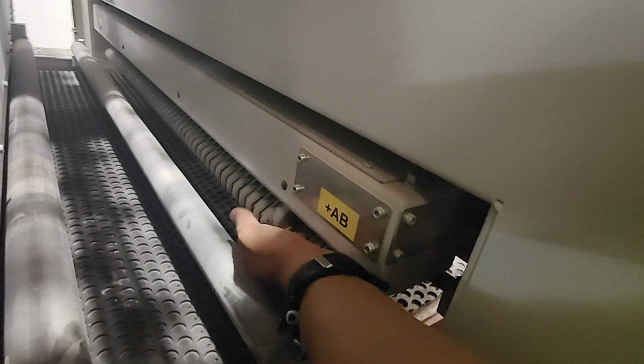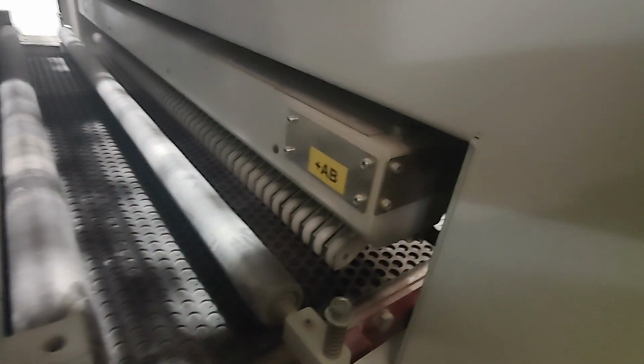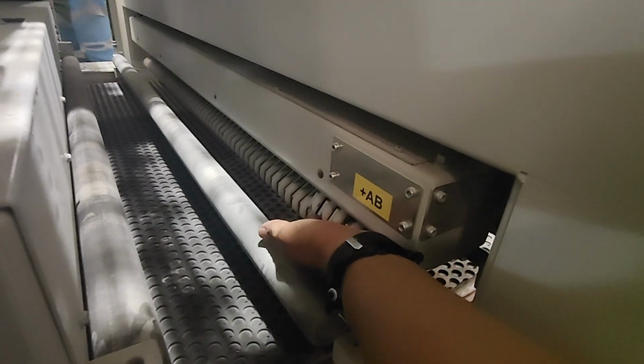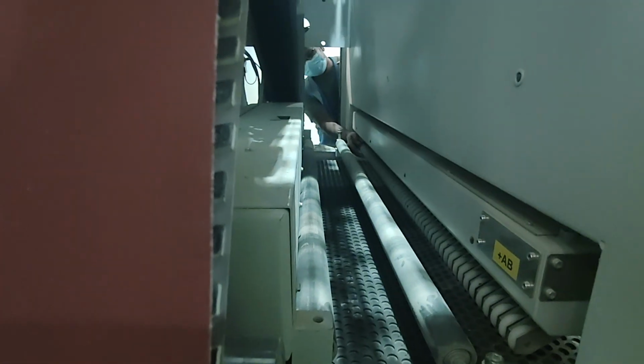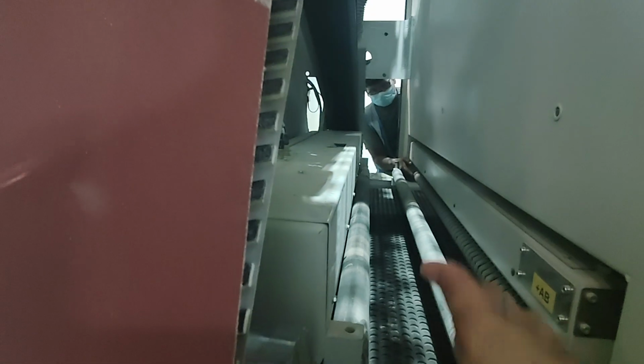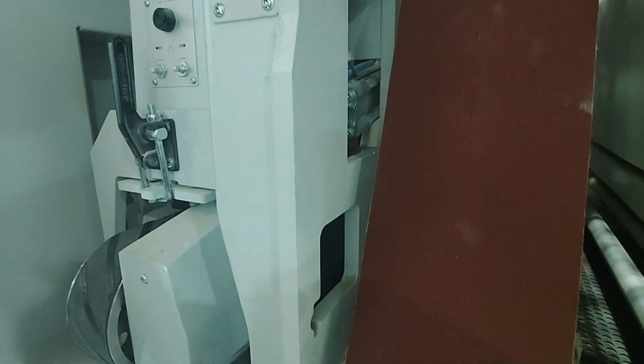Yes, basically these are all sensors, no? Yeah, so it's a sensor. Those will give the input, and inside of these there will be small cylinders which will actuate. After sensing the size, the dimension of the panel, they will give signals to the area where it will actuate and push the sanding belt. All right, fine. Okay, and also check all the pneumatic cylinders, pneumatic hoses, or any leakage during preventive maintenance.